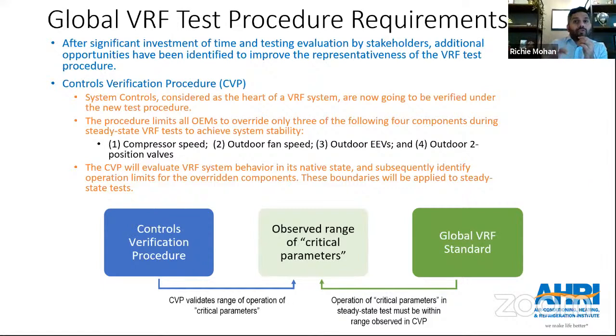And once we get a range, or rather an operation range, for those critical parameters, then that range can be carried into the steady state test, and that range will become your boundaries. If you were to lock in your compressor speed, your compressor speed settings cannot go beyond the range that you had observed during the CVP, when the system was in its native state, without any external touching from the lab personnel or the manufacturer for that matter. In this way, we try to hone in as much as possible on how the system would really perform on its own in the field.